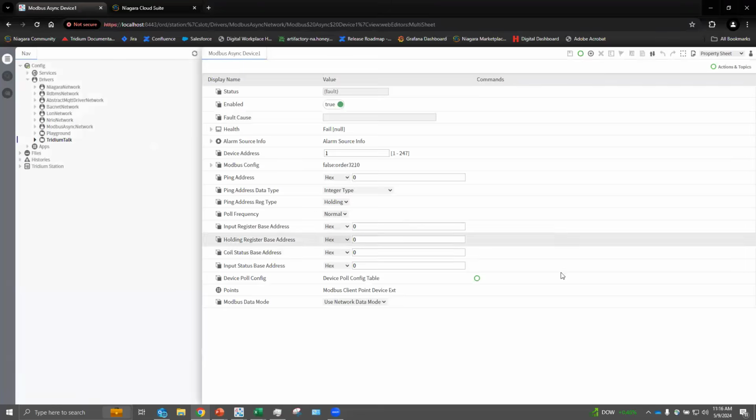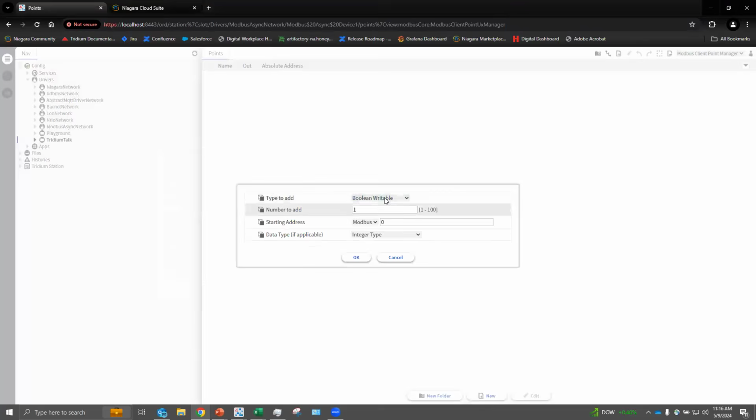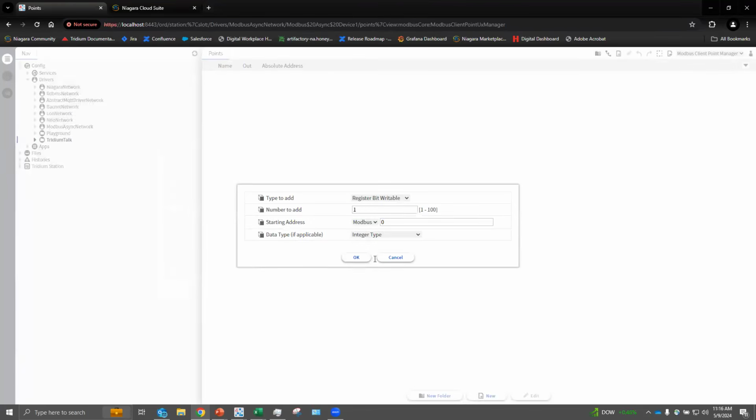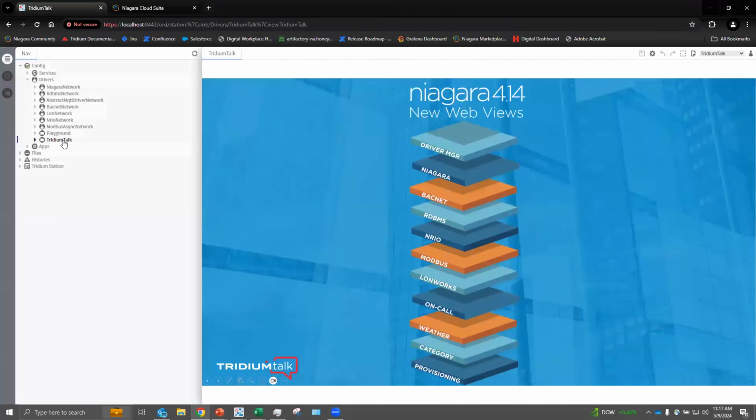But as you know, with Modbus, you actually have to add the points, so there's no essential discovery of those. And so through that, that's when you'd start adding your Modbus points accordingly. But again, you could build that all in. Of course, this is going to fail at the moment, given the starting address that I defined therein. But again, you have that capability to do full, complete, end-to-end management setup of a Modbus network.